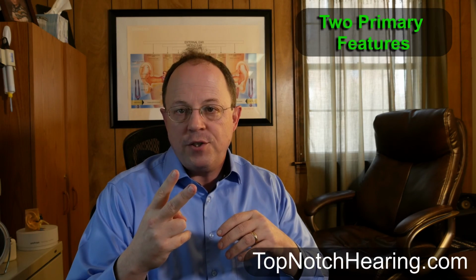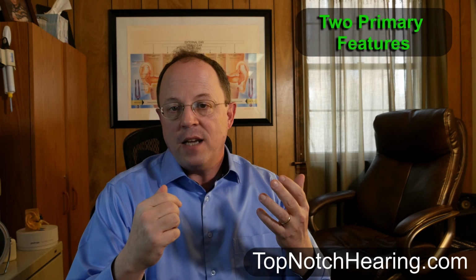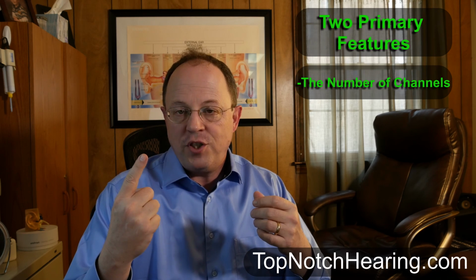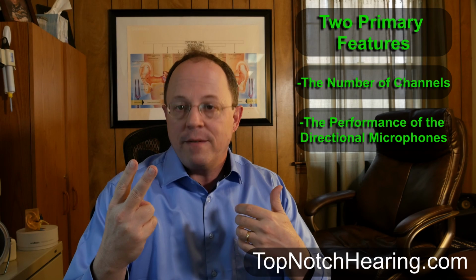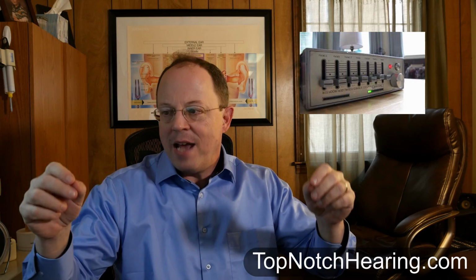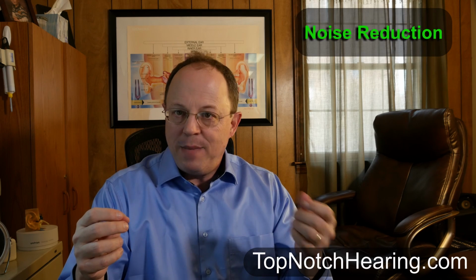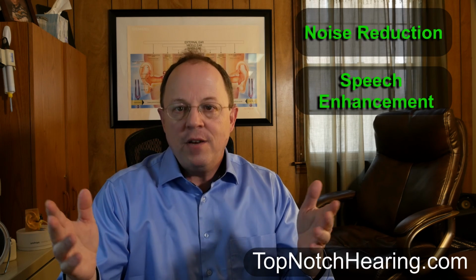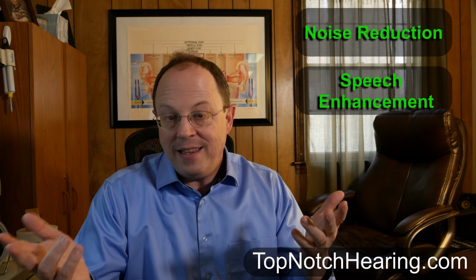There are two primary features that separate the performance of each technology level: the number of channels, and the performance of the directional microphones. To understand channels, think about old stereo equalizers - the more channels or bands you had, the more precise you could be in adjusting the sound. Hearing aids are similar, but we're doing more than adjusting volume. In each channel, hearing aids apply noise reduction and speech enhancement. So the more channels you have, the more clear or clean the speech will sound.